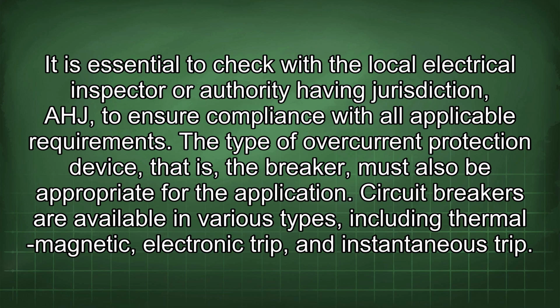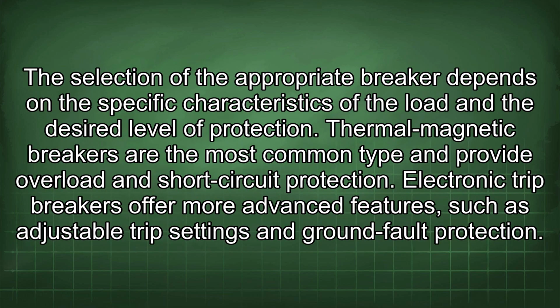The type of overcurrent protection device, that is the breaker, must also be appropriate for the application. Circuit breakers are available in various types, including thermomagnetic, electronic trip, and instantaneous trip. The selection of the appropriate breaker depends on the specific characteristics of the load and the desired level of protection. Thermomagnetic breakers are the most common type and provide overload and short circuit protection. Electronic trip breakers offer more advanced features, such as adjustable trip settings and ground fault protection.